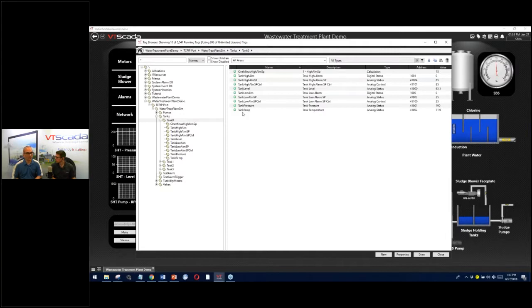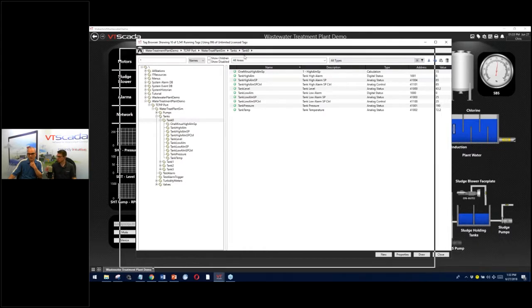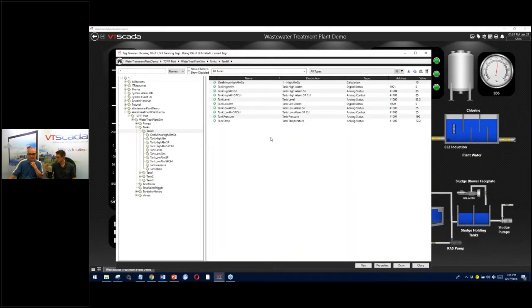So you don't have to overload all your tag names. That's right. So I'm not having to go into each of these and update them. I just update one thing in the tank settings. And you can then also create a parameterized page or a widget that will accept that parent tag as a single parameter and then populate everything. People who have lift stations and other things, that's generally what they're doing. They'll make a tag type that has all of these in them, which essentially are shown as children tags, but really are child parameters. So they just make the new tag, drop it in, put in whatever the IP address is to reach that, and then they can also draw those as a single object.